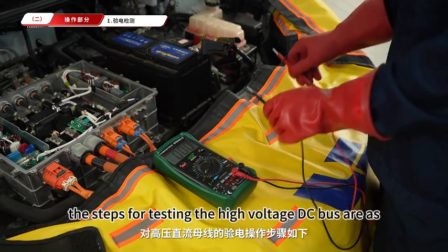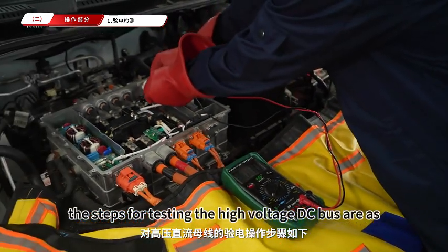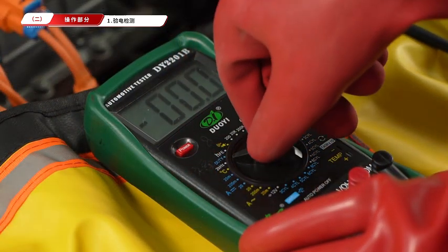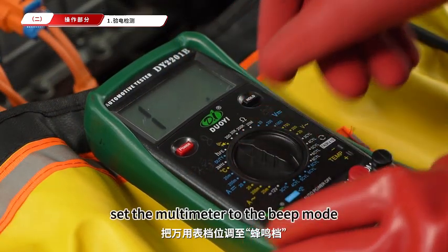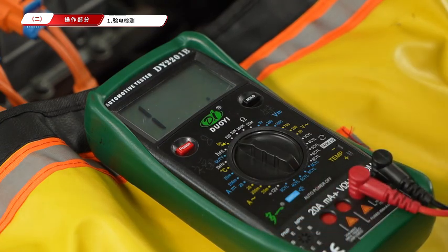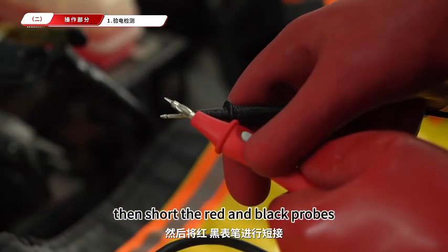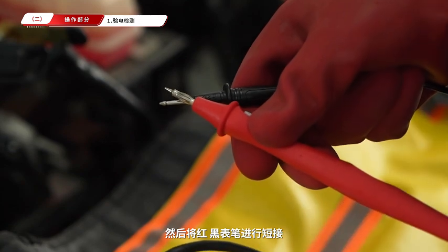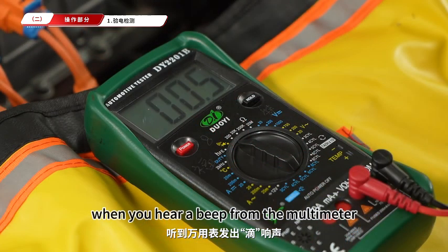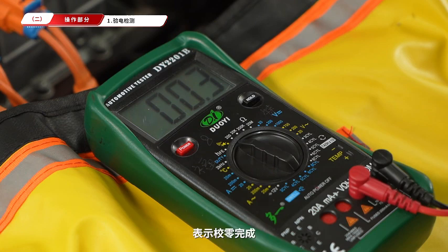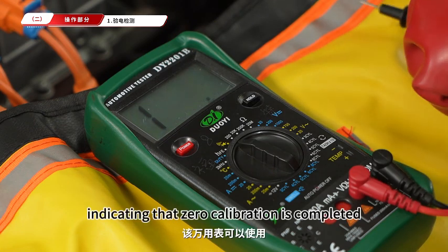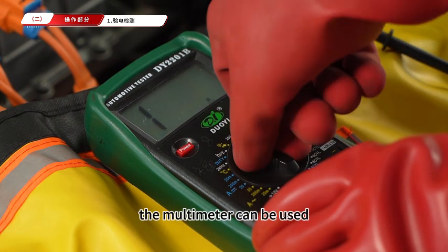The steps for testing the high voltage DC bus are as follows: first, turn on the multimeter switch. Set the multimeter to the beep mode. Then short the red and black probes. When you hear a beep from the multimeter, indicating that zero calibration is completed, the multimeter can be used.